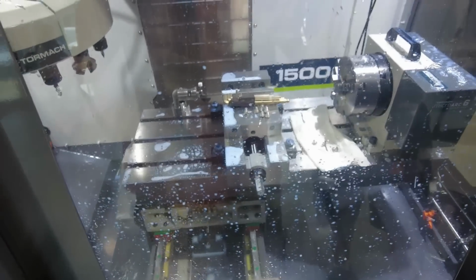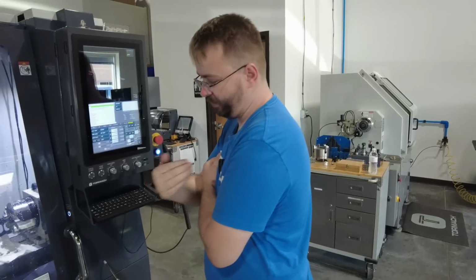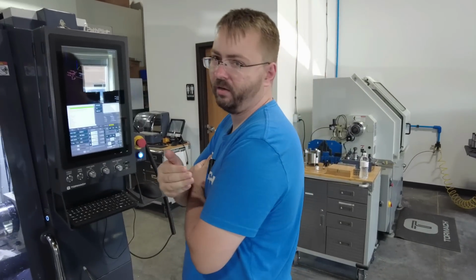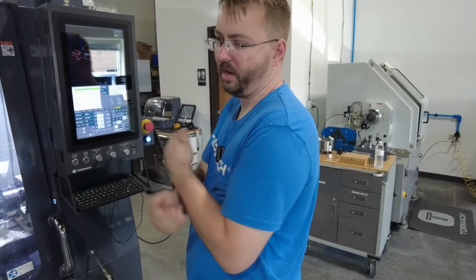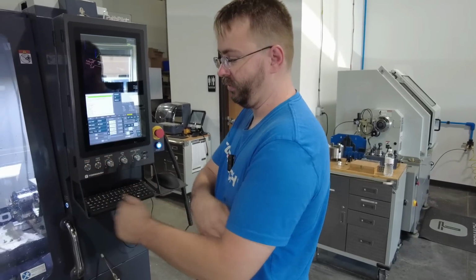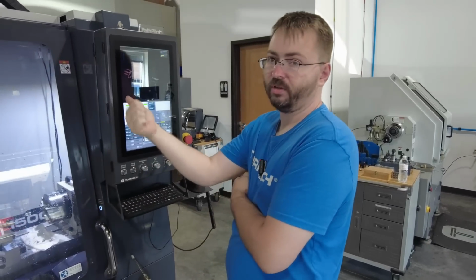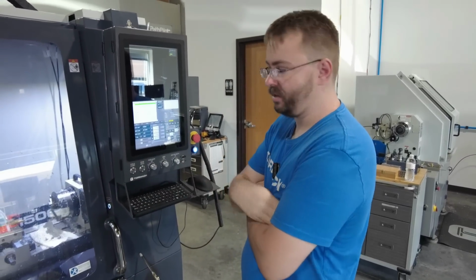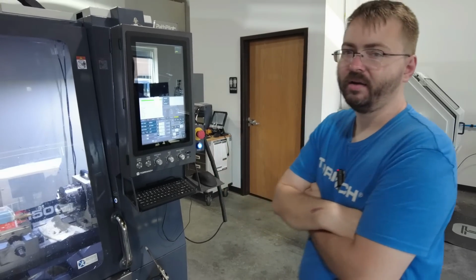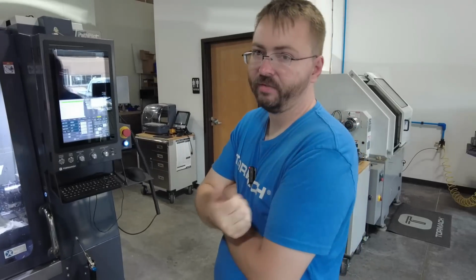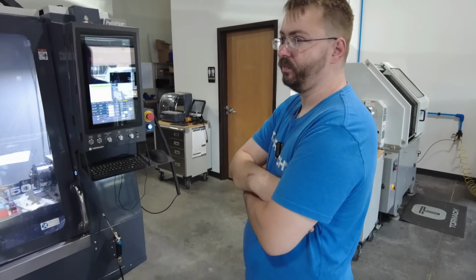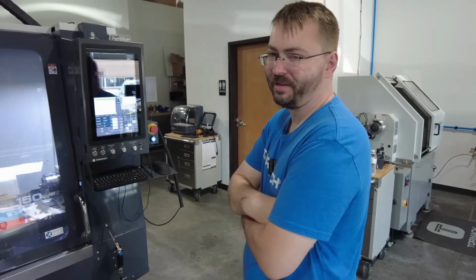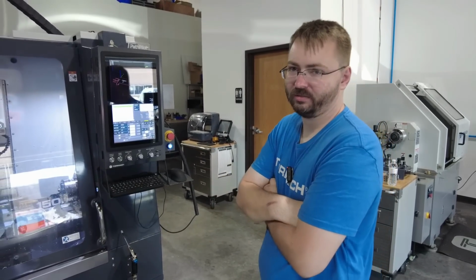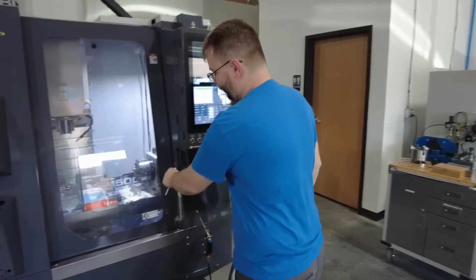Same as before, it finds the end of travel and then looks for an index pulse. We run into the bumper at the end of travel, notice the torque spike from the load on the motor, and back up to the index pulse of the encoder. So you can remove the batteries from every single drive and still do hard stop homing, and until you power off the machine, not even e-stop, it'll retain the reference. That feature actually came later in development, and our prototypes ran that way for 6 months, working perfectly fine.